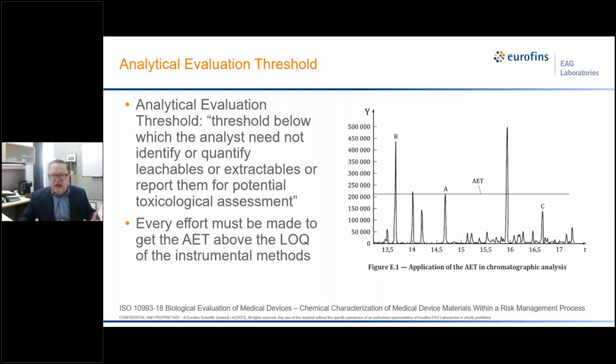Anything above the analytical evaluation threshold needs to be identified and semi-quantitated, and anything below it doesn't necessarily need to be identified or quantified. In essence, your LOQ must be below your AET, and if your sensitivity isn't sufficiently low, then you may not be able to demonstrate that you can detect down to the AET. So that really is the sensitivity limit that you need to demonstrate.